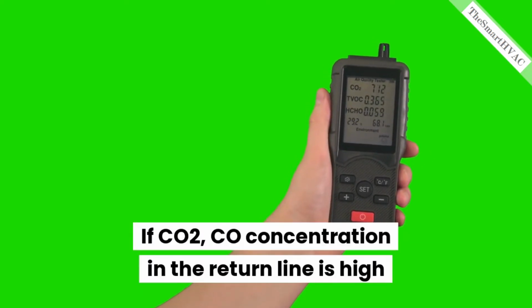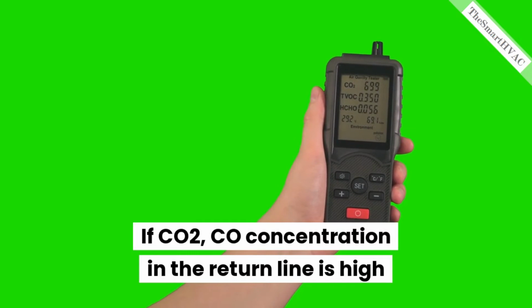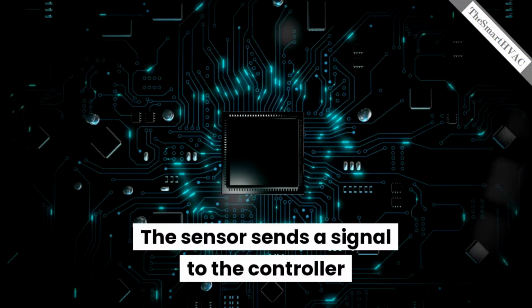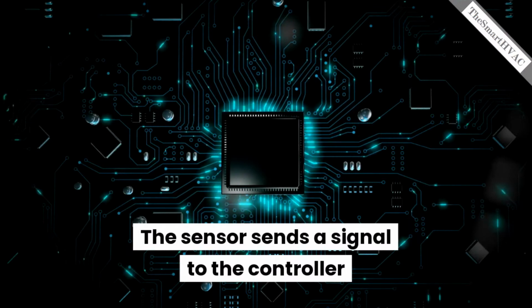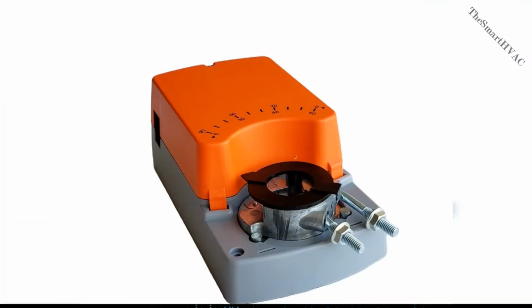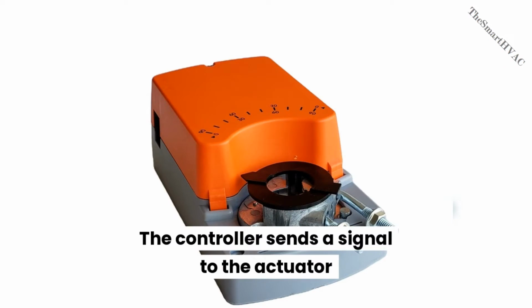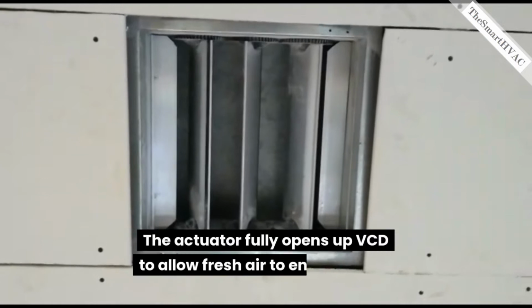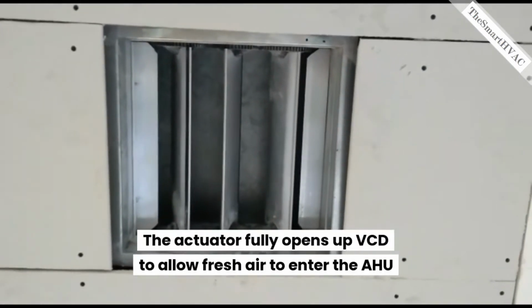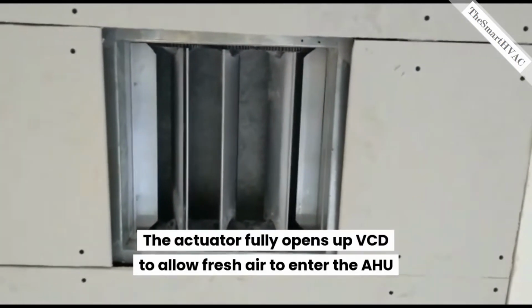If the CO2 or CO concentration in the return line is high, the sensor sends a signal to the controller. The controller sends a signal to the actuator, and the actuator fully opens up the VCD to allow fresh air to enter the AHU.